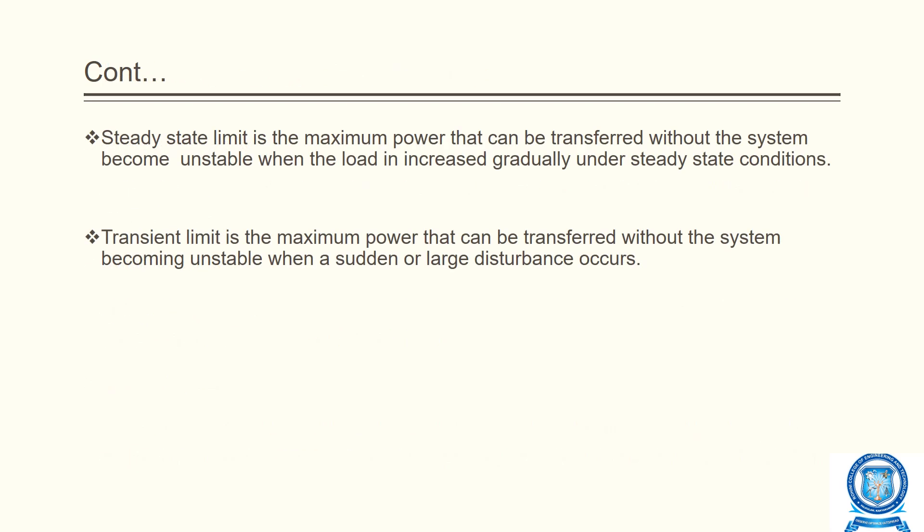The steady state limit is the maximum power that can be transferred without the system becoming unstable when the load is increased gradually under steady state conditions. The transient limit is the maximum power that can be transferred without the system becoming unstable when a sudden or large disturbance occurs.